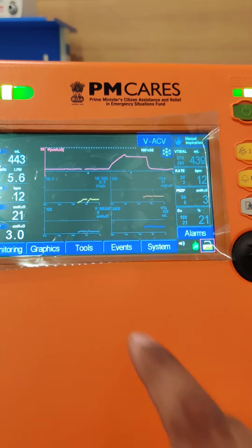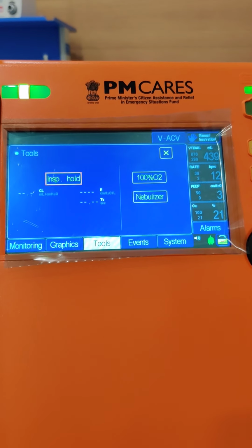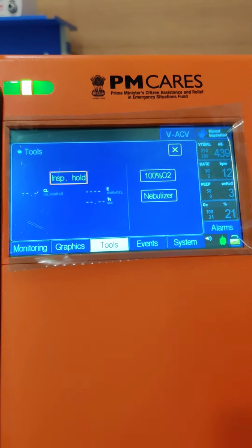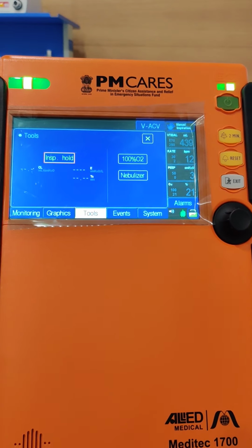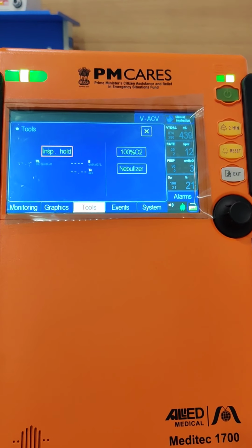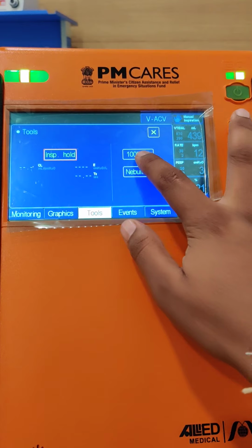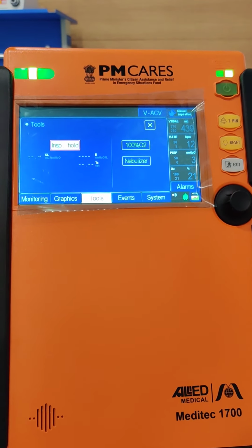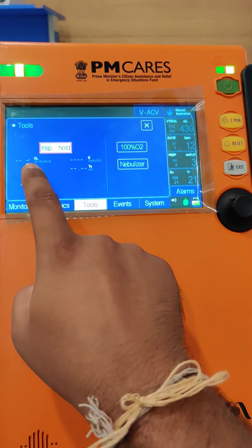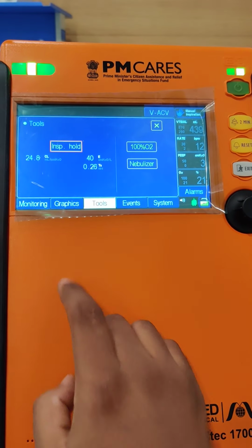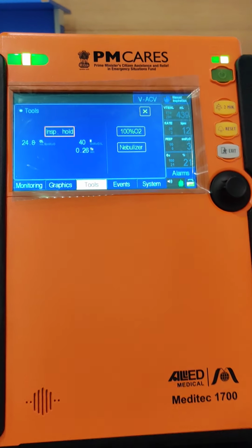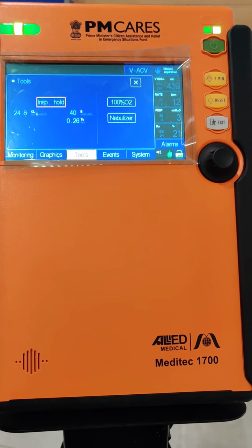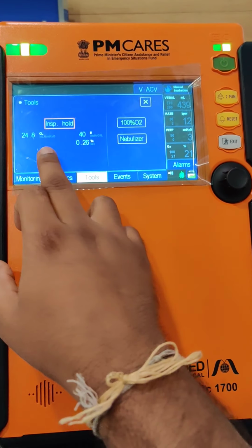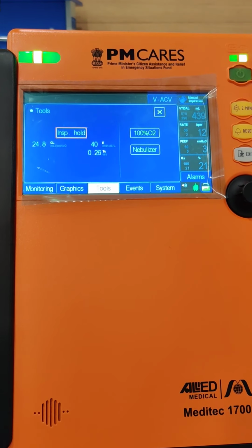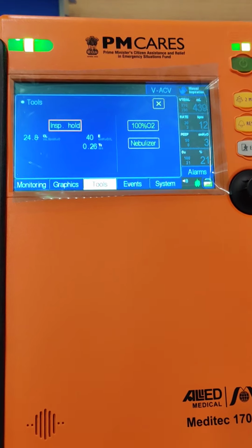Now coming on to the next shortcut key, that is tools. In this you can use 100% oxygen for suctioning. If you want to pre-oxygenate the patient at 100% before suctioning, that option is available in the tools, and we have also given the inspiratory hold. For calculating the breath-by-breath compliance, the elasticity and the time constant, you have to press the inspiratory hold. The ventilator will give a pause to the patient, and it will display these three parameters: the compliance, the elasticity and the time constant.